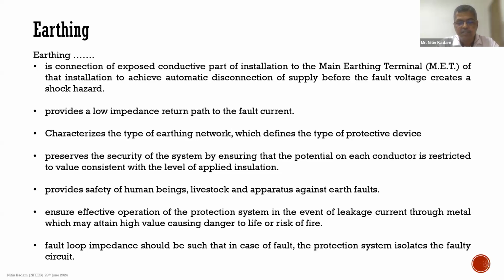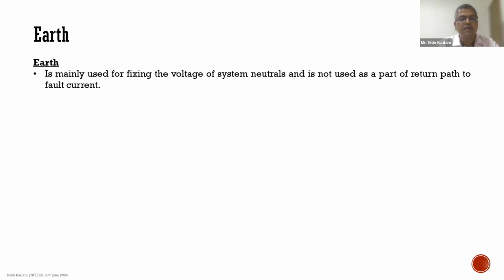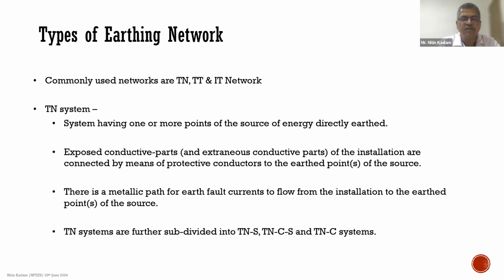This metallic earth return path also defines the fault loop impedance value, and this has to be verified on the site, as I was mentioning in the previous slides. Now, when we talk about earth, it is generally not used as a part of the return path to the fault current. It is mainly to fix the voltage on the system neutral, so that there are no shock hazards available on the exposed conductive part due to indirect contact. So what are the kinds of earthing networks we have? There are basically TN, TT, and IT networks, and the TN system is further divided into TNS, TNCS, and TNC systems. Let us see how these networks look.